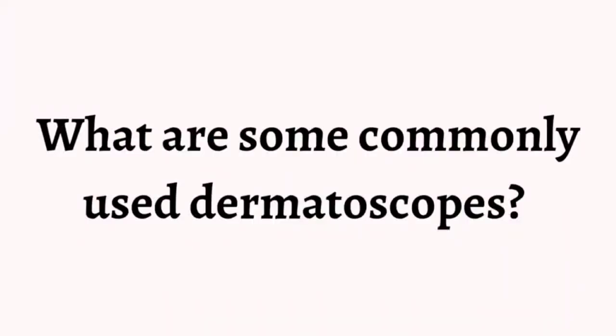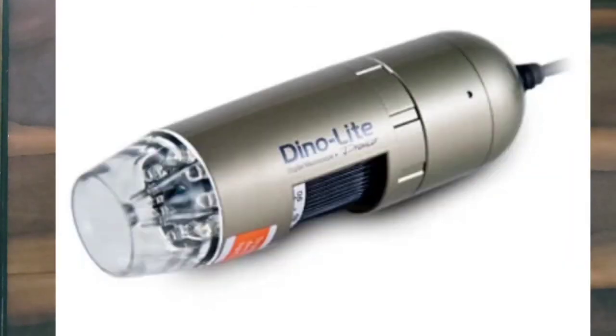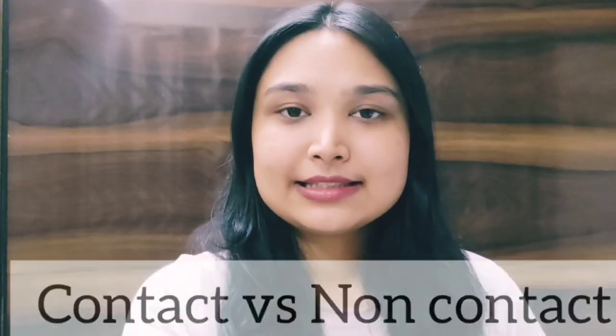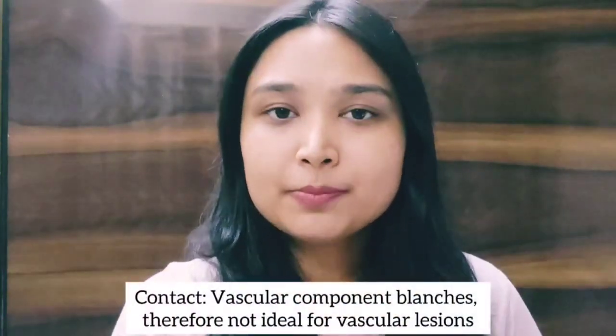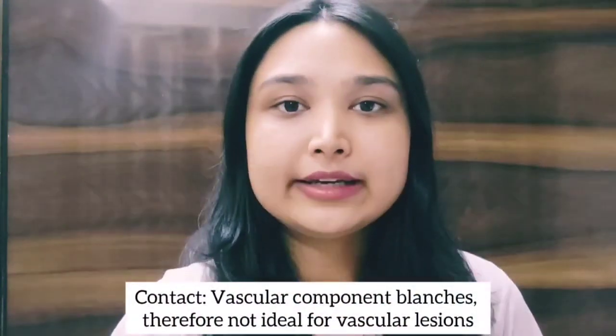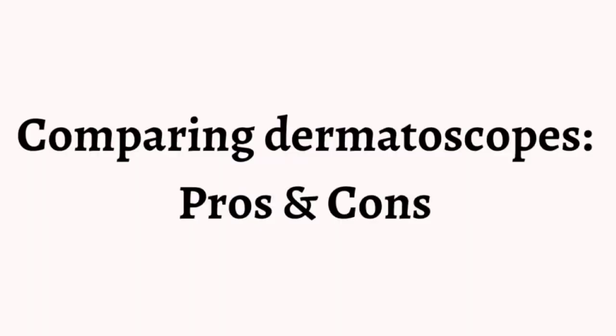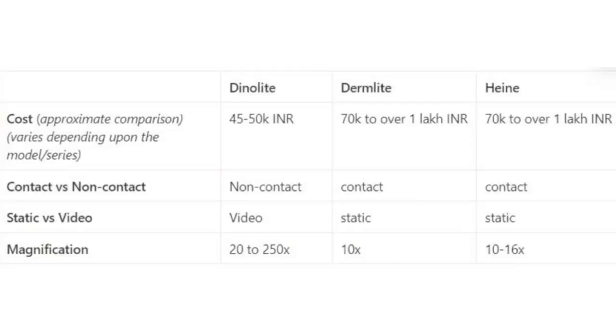There are two types of dermoscopes available in the market: contact dermoscopes like DermLite and Heine, and non-contact dermoscopes like Dinolite. Contact dermoscopy means the lens of the dermoscope will come in contact with the lesion during the examination. The disadvantage of contact dermoscopy is that since the lens puts pressure on the lesion, the vascular component of the lesion blanches. This problem does not arise in non-contact dermoscopes like Dinolite, where the lens does not touch the lesion.